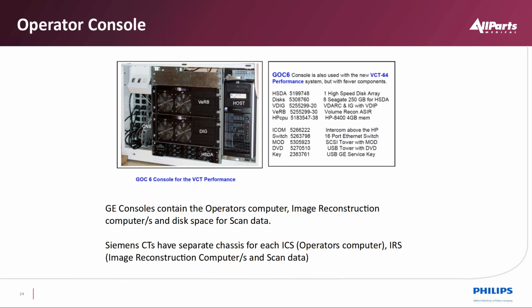This would be an example of an older console where we have the host operating system. In the case of GE, that's a Linux machine. That's what the operators are interfacing with. So we have a monitor for scanning, a monitor for image recon display. And so the host is then working with the DIG, which is basically the controller for recon. And the VeRB is a special added recon for high-speed recon. And then the high-speed disk array, which is the raw data array that is used for the recon subsystem. So the recon subsystem is much bigger than the host in this one.